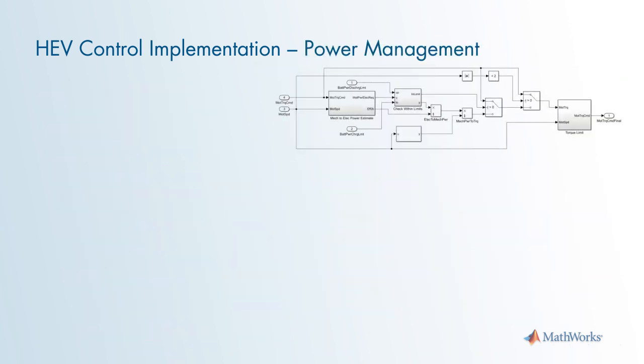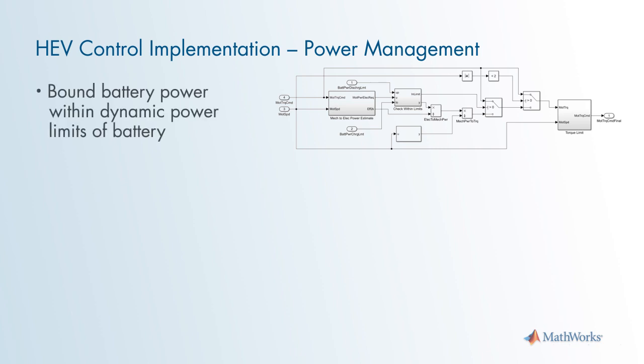The last detailed implementation function I want to discuss is power management. Power management attempts to keep the instantaneous battery power within the dynamic discharge and charge power limits of the battery. Typically, a battery management system, or BMS, dictates the amount of discharge or charge power depending on the conditions of the battery, such as state of charge or temperature.